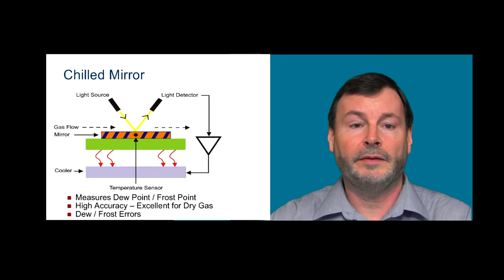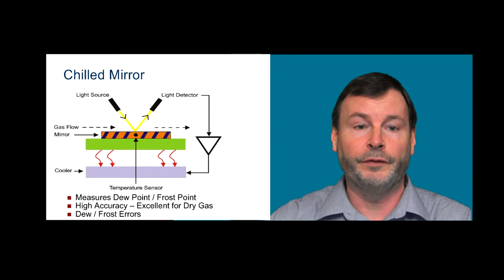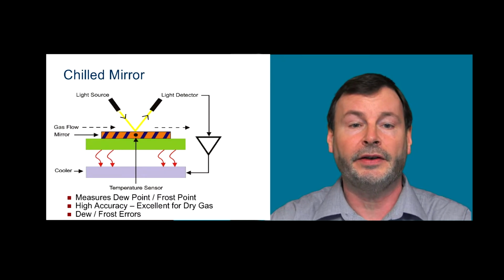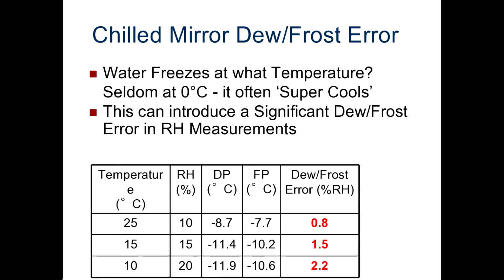Now, this uncertainty of dew versus frost can lead to significant humidity errors. Looking at the table here, we can see if we have 25 degrees C and 10% relative humidity, if there's dew forming on the mirror, it will be at minus 8.7 C. But if it's frost, it's minus 7.7 C. Now, if the temperature was 15 C and the humidity was 15%, again, you can see substantially different temperatures of the mirror if it's dew or if it's frost. And at 10 degrees C and 20%, it's just that much different.